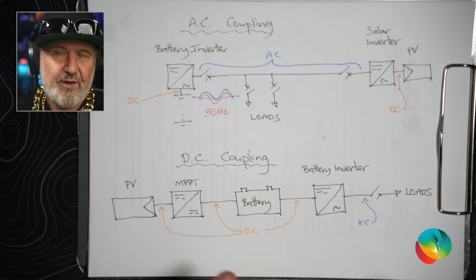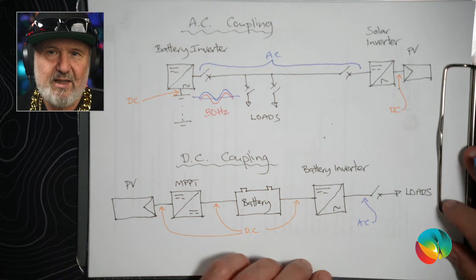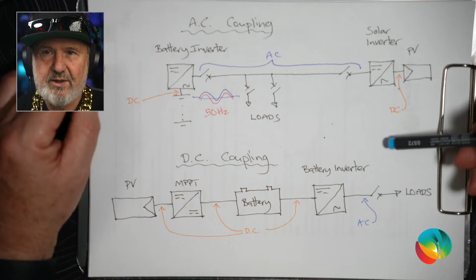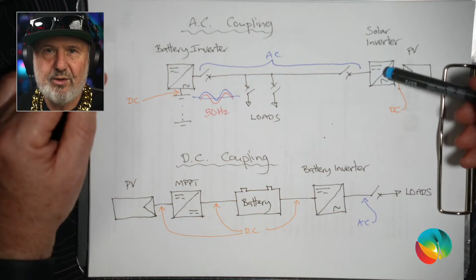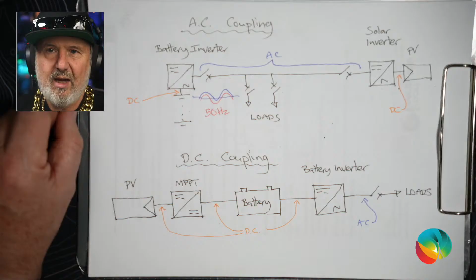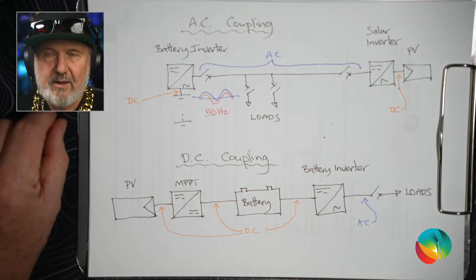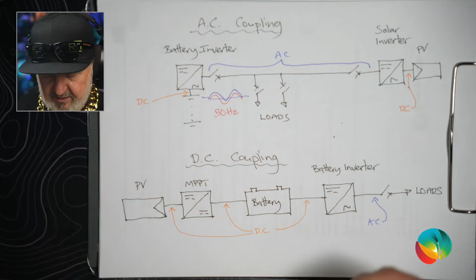So this is a very popular configuration. What's so good about it is, for a start, it's scalable. So you can actually have multiple solar inverters, and they can parallel using their own internal software, and they don't actually have to be the same brand. So for instance, this could be brand A, this could be brand B, but I've drawn this without showing a grid. In a grid connected system, you may have another input, which would be the grid. And so our battery inverter may actually have a grid input. So I'll put grid here.